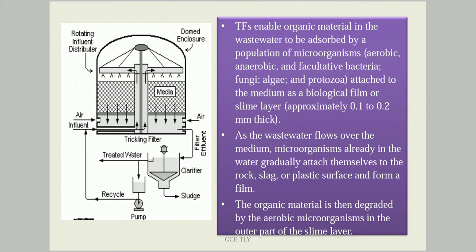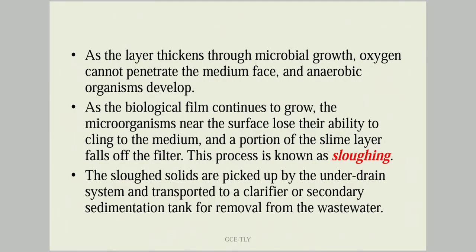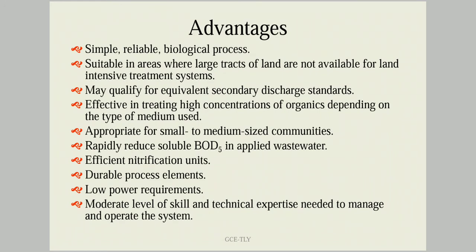The microorganisms form a film over the media and act on the organic matter, breaking it down into stable matter, growing as a slime layer. As the layer thickness increases due to microbial growth, oxygen cannot penetrate through, so anaerobic organisms develop. As the biological film continues to grow, it may lose its ability to attach to the media and falls off — this process is known as sloughing. These sloughed particles are removed through the drainage section with the treated water and separated in the secondary sedimentation tank as sludge.